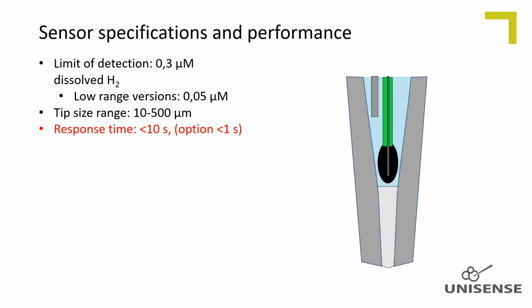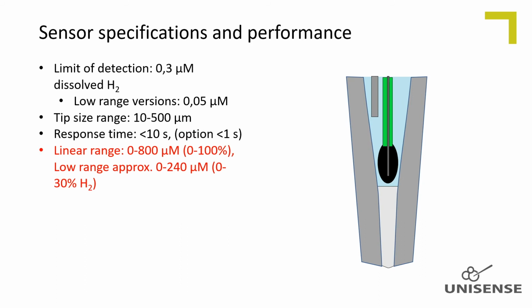The response time is a function of the hydrogen diffusion path length into the working electrode and chosen to obtain the best compromise between sensitivity, response time, and stirring sensitivity. Hydrogen sensors can be made very fast responding, down to less than 1 second. Our standard sensors respond linearly to dissolved hydrogen in concentrations from 0 to supersaturated solutions, as well as in gas samples from 0 hydrogen to pure hydrogen gas.